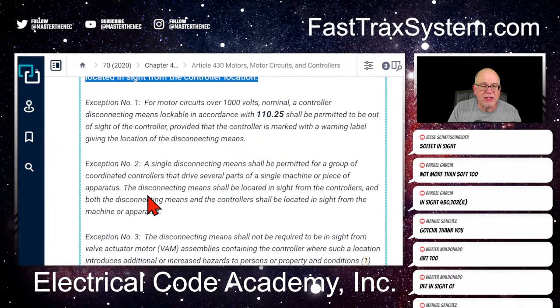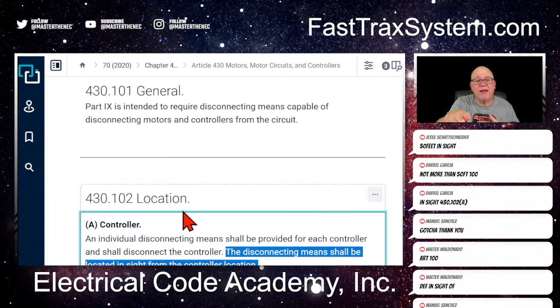Article 100 would have worked as well, but you also get it inside of here. If you want the definition of within sight of, go to Article 100, and that's where you'll learn it means within 50 feet. So funny enough, if the disconnect is within sight but it's 51 feet away, it's technically not within sight even though you can still see it - by the code, it's not within sight.